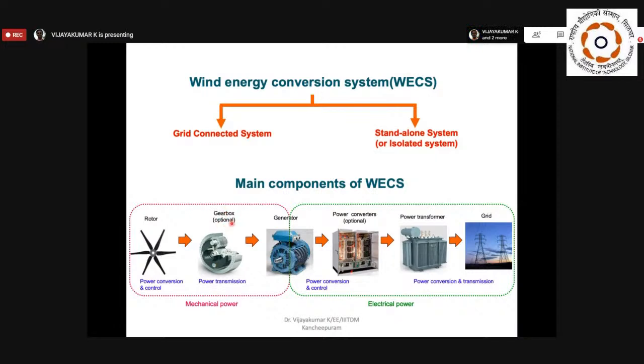Here again, they put the gearbox as optional. Why did they mention it as optional? Nowadays people are working on gearless wind turbines, because the gearbox cost is higher, around 30% of the cost. So people are working to eliminate the gearbox. Once you eliminate the gearbox, what will happen? The rotor speed is 50 rpm to 100 rpm, and you have to match it with the generator. So you have to work on a generator that generates power at low speed. Nowadays people are working with permanent magnet synchronous generators, because they can generate power at low speed itself. So for gearless wind turbines, people are working with permanent magnet synchronous machines.